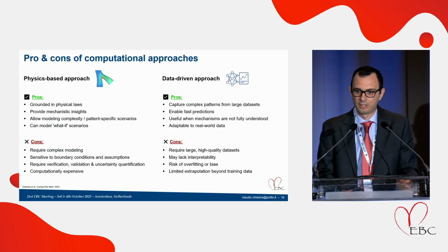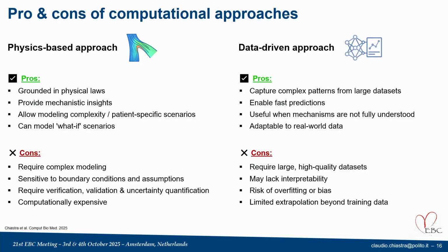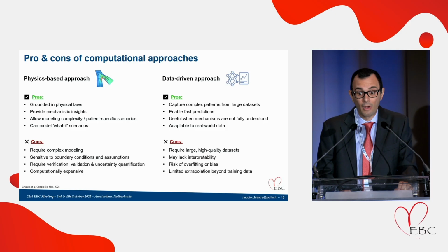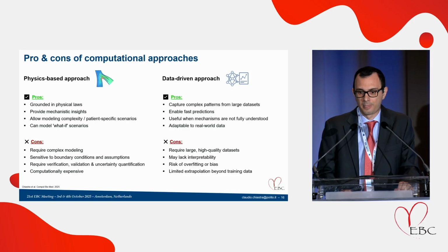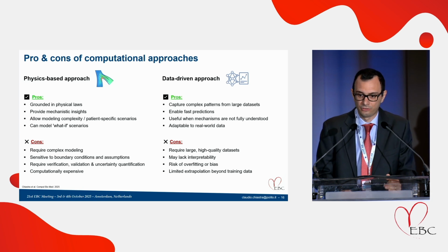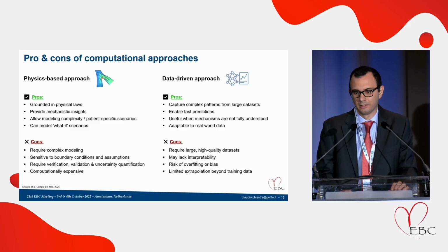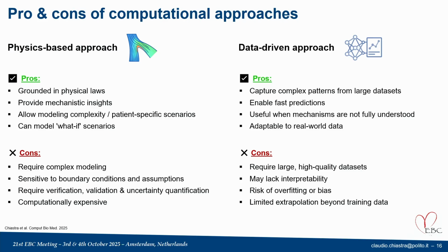So just to summarize the pros and cons of computational approaches, for the physics-based approach, they are grounded in physical laws, they provide mechanistic insights, they allow modeling complexity, so this means that they can be used for analyzing patient-specific scenarios, and they can model what-if scenarios. However, they require complex modeling, they are sensitive to boundary conditions and assumptions, they require verification, validation, and uncertainty quantification, and this is also needed for the regulatory approval of the devices. And they are computationally expensive in general.